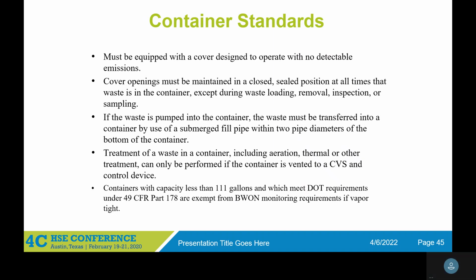A lot of people get confused, especially in Texas, but I don't think I have anybody here from Texas. There are other rules that overlap, like MSS, maintenance, startup, and shutdown, that mandate more for containers. But BWON is simple, just cover it unless you're filling it, right? And do your inspection and monitoring, which we'll go over. Now, there's one thing, if it's less than 111 gallons, it's small enough that it's not required that you control it. Small thing.